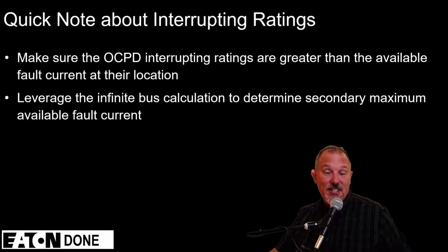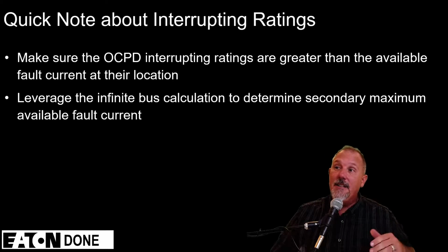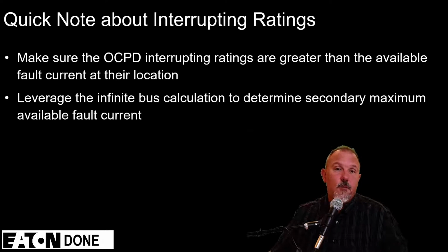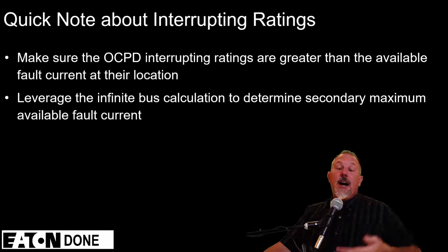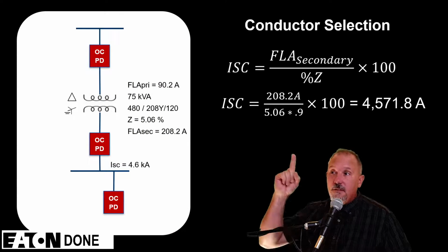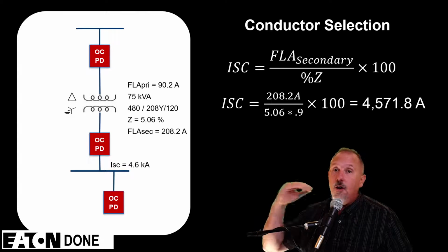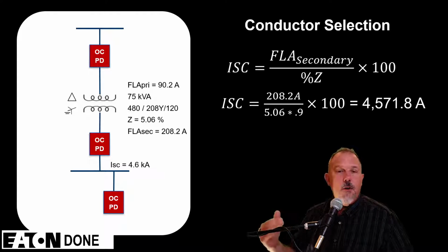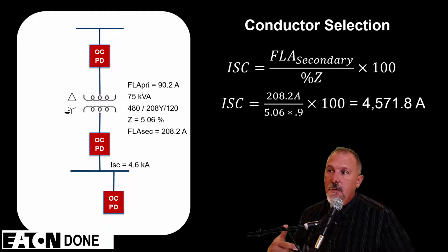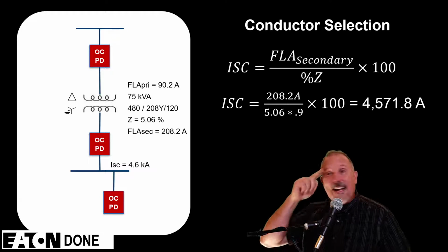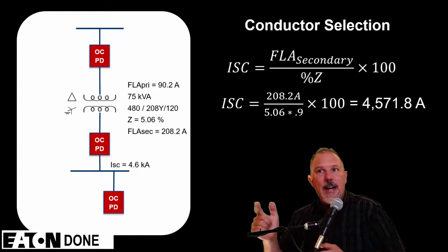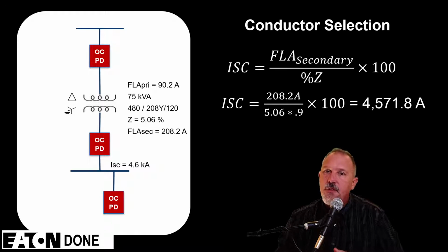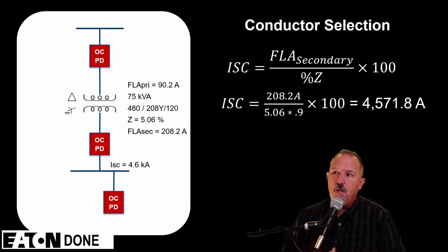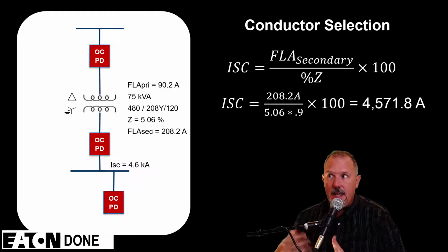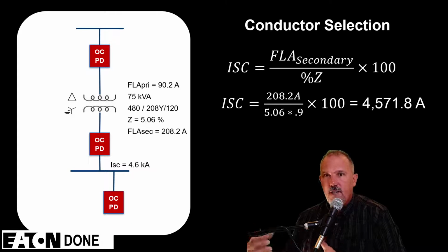We referenced a couple code sections in this 15-20 minutes, and next we have to make sure that we pick the right overcurrent protective ratings from an interrupting rating perspective. I leverage the infinite bus calculation. There's my equation: you take the full load amps over your percent impedance times 100, so it's 208.2 secondary, 5.06 times 0.9. The reason I did 0.9, I didn't do this last time, I added 0.9 in there because that nameplate value, based upon the standards when we build transformers, I'm allowed plus or minus 10%.